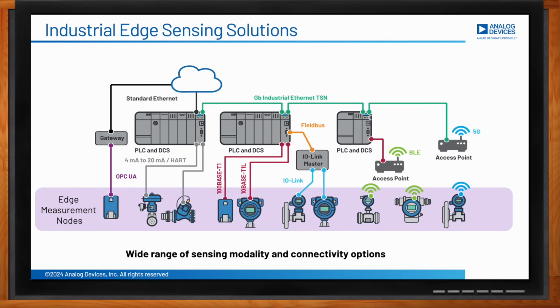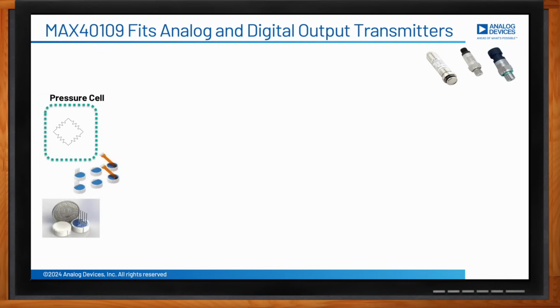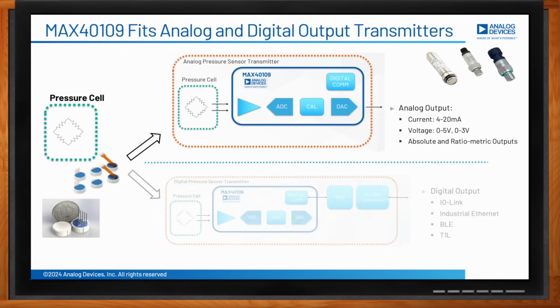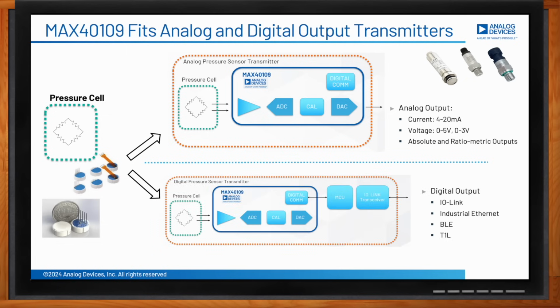So, Maurizio, pressure sensing seems to be one of the most popular applications in intelligent edge. Does ADI have any solutions for that? ADI has a brand new solution for pressure sensing, which in relation to the edge measurement nodes, in this case a pressure sensor transmitter, enables all forms of communication, both analog and digital. This new solution is called MAX40109. The MAX40109 interfaces directly with the pressure sensor element and enables solutions for both analog and digital pressure sensor transmitters. The former uses analog standards such as 4 to 20 milliamp current loop and 0 to 5 volts analog voltage output, both in absolute and ratiometric fashions.